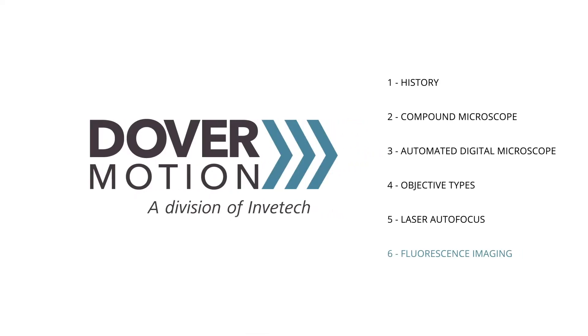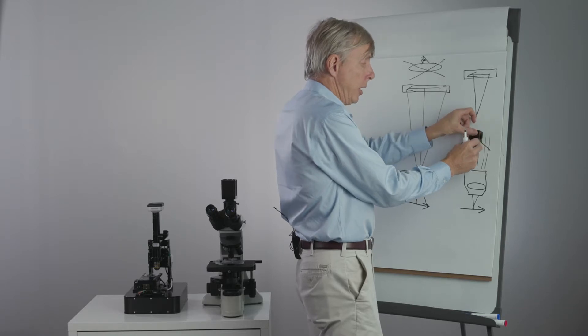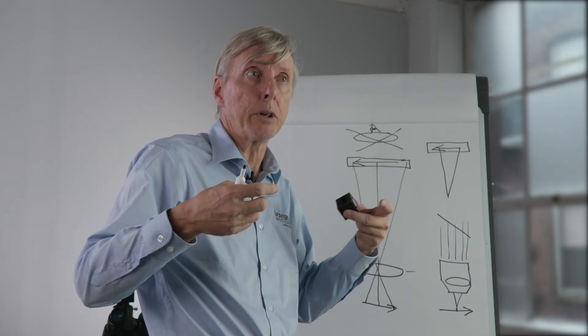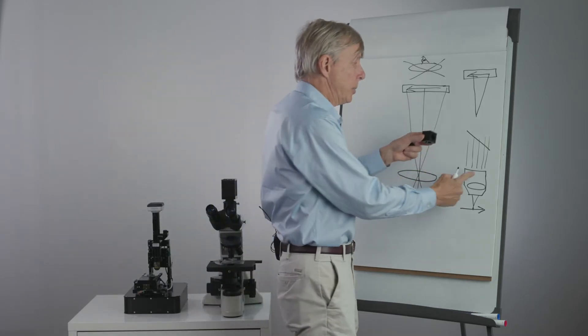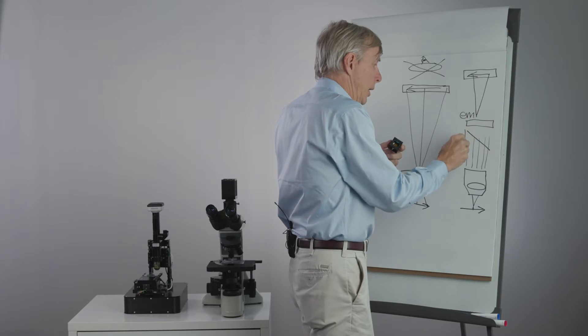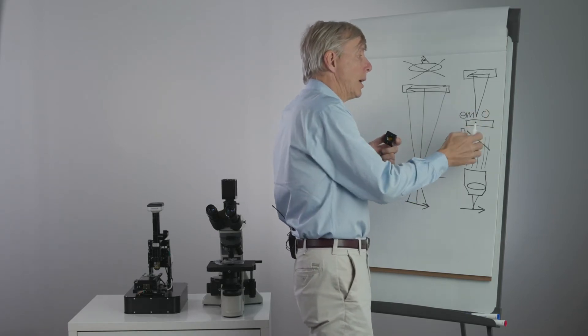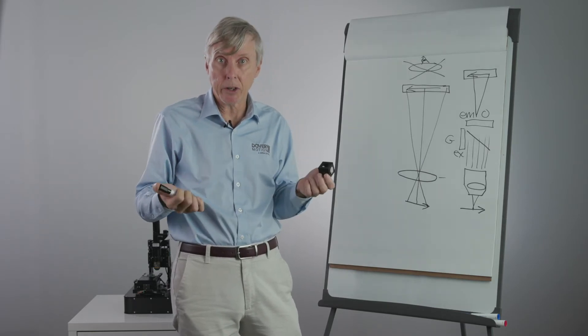Another common optical element introduced into the infinity space is a fluorescent filter cube. It consists of a beam splitter: excitation light enters from the side through an excitation filter, is sent down toward the sample, and the sample — labeled or stained with fluorophores — will fluoresce, emitting redder light. When that light comes back up, it transmits through the beam splitter through an emission filter. For example, green light goes in and orange or red light comes out, allowing us to see fluorescent signals valuable in both DNA sequencing and diagnostic applications.